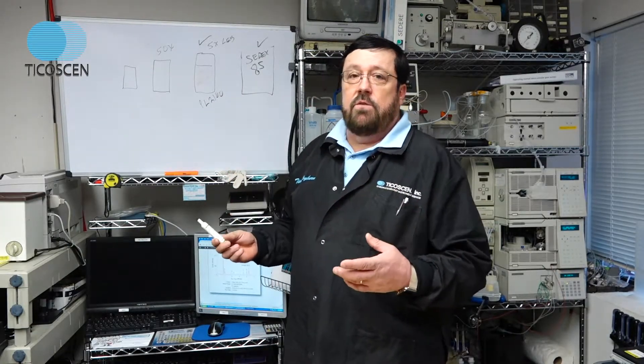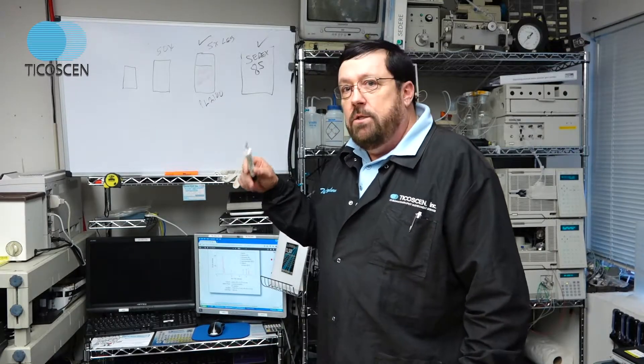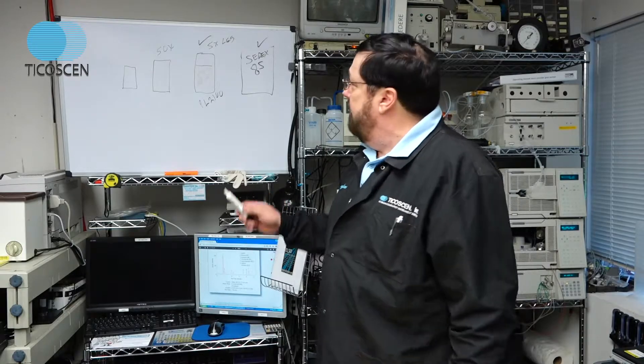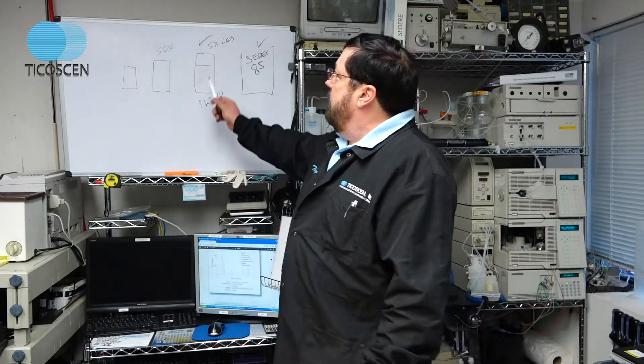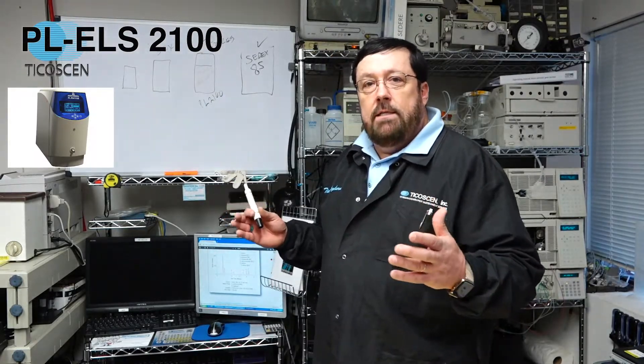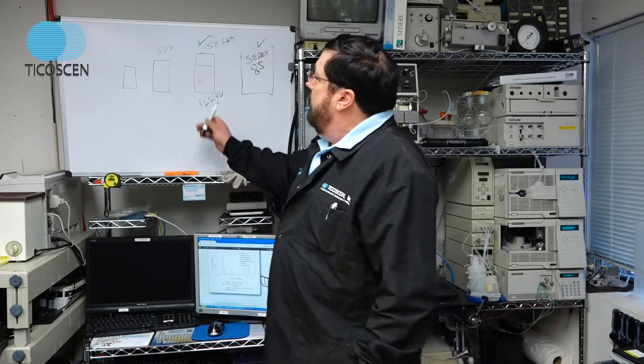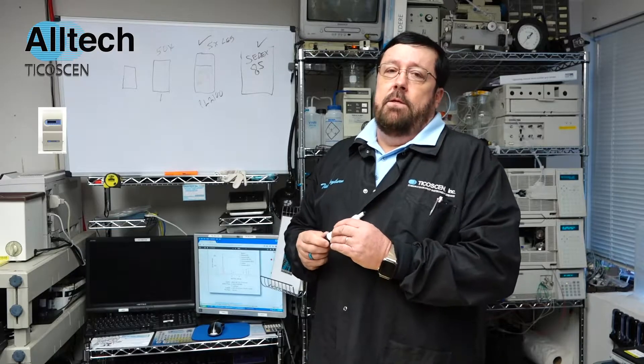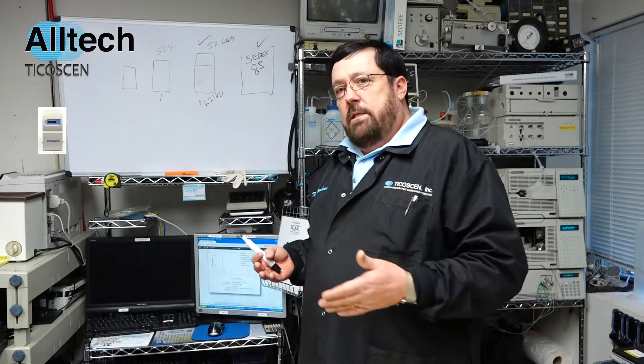I have a client with one of each of these because they do random method analysis for clients from all over the country doing compound analysis. If they've got a rare sample — say some rat brain tumor extract that took two years to grow — and they want to do a full 40-injection assay with very low concentrations, they need the Sedex. If you have an industrial or food-grade product where you're not sample-limited, you might go to a Polymer Labs style detector — kind of the in-between, the middle-of-the-road detector. The lower-sensitivity Alltechs are for industrial chemical companies with tons of petroleum product or plastics who can inject huge concentrations to compensate for the detector's lack of sensitivity.